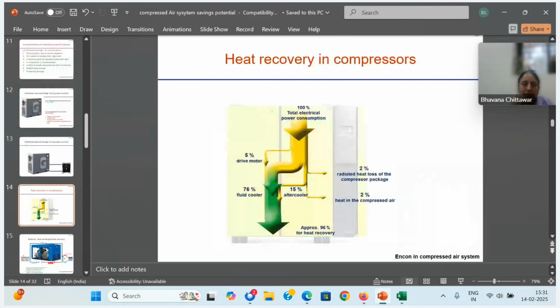Then heat recovery in compressors. See, as I mentioned, 100% of the heat can be recoverable, but some heat goes away. The drive motor takes away some 5% heat. Your oil cooler, 76% it is carrying, after cooler 15. So total 96, 2 or 3% heat will be dissipated in the compressor itself. That cannot be recovered. Otherwise, more than 90% of the heat, precisely 96%, but 90% heat is available. This is a golden energy actually. We are throwing away the heat within the compressor room and again increasing the power.